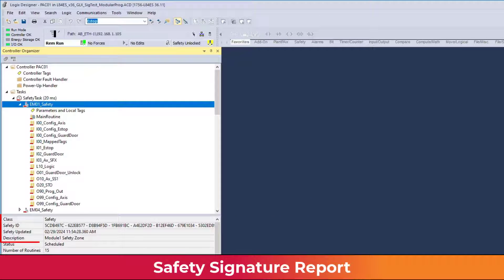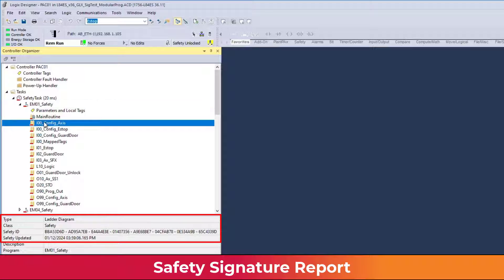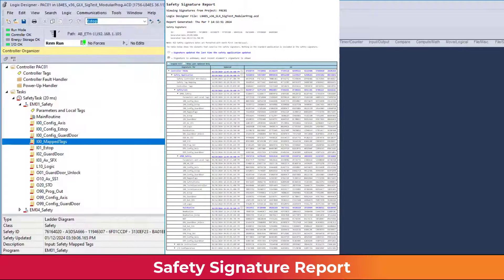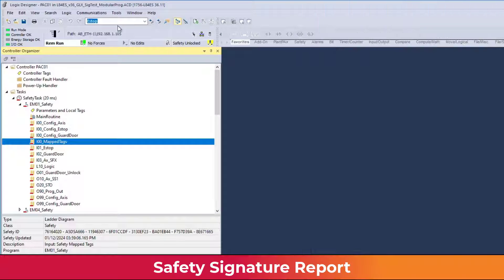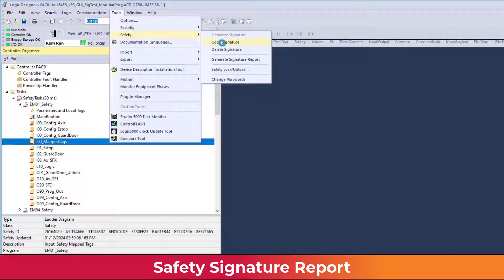The Quick View pane provides individual element signature status to the online user. The safety signature report provides a holistic, color-coded signature status of the entire controller. From the Tools menu, select Safety, then Generate Signature Report.